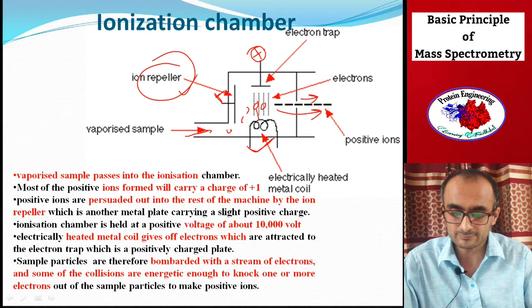The second stage is acceleration. Now these ions are accelerated so they all have the same kinetic energy, and they are coming from the ionization chamber that is kept at 10 kilovolts. There are 3 slits here. The last slit is kept at 0 volt. So the first is a maximum of 10 kV, in between you have some intermediate voltage, and the last one is 0 volt. As a result, the beam coming from the ionization chamber is accelerated in the direction of the detector, and before that it is analyzed. So this is the beam of ions which is focused into the analyzer.